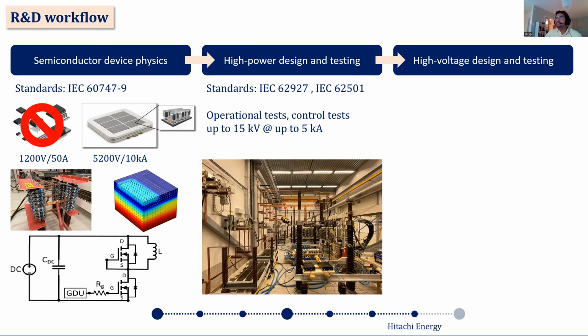And this is just one of our labs, but I can't show you a lot of stuff because of confidentiality. We have massive labs that can supply a lot of power pumping in through the converter. And then we do operational and control tests. So operational tests to check if we actually replicate an HVDC station in the lab. And then we check if the control system is working correctly. We go through different kinds of control operation areas. And the major standards that we use here are the two HVDC standards, 62927 and 62501. 62501 is for HVDC, 62927 is for STATCOM valves.